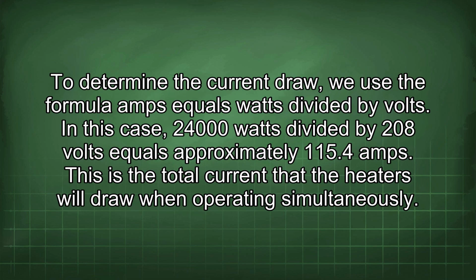To determine the current draw, we use the formula amps equals watts divided by volts. In this case, 24,000 watts divided by 208 volts equals approximately 115.4 amps. This is the total current that the heaters would draw when operating simultaneously.